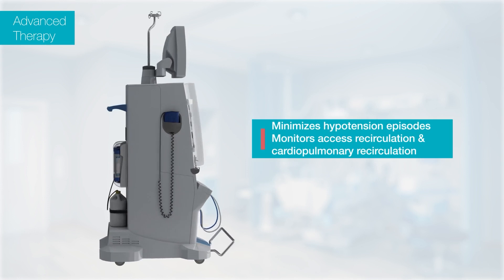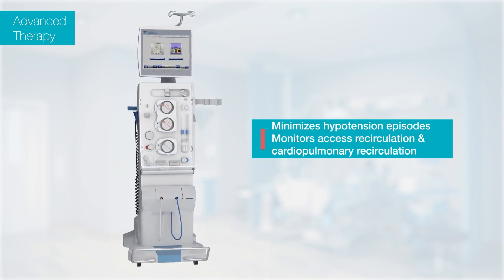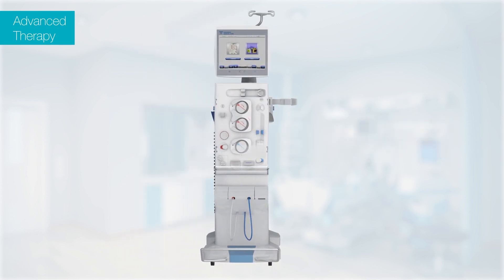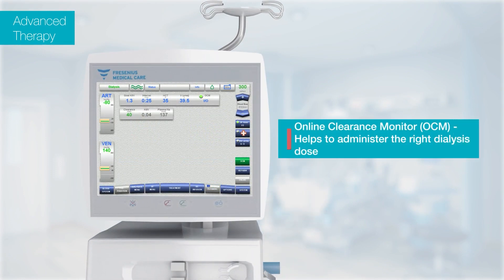The 5008S therapy system helps to minimize hypotension episodes and monitors access recirculation and cardiopulmonary recirculation with the help of the following features. The online clearance monitor enables an automatic intra-dialytic measurement of the delivered dialysis dose.